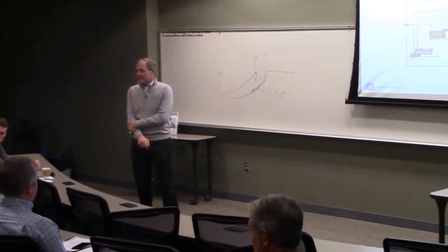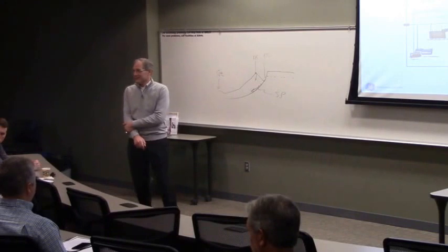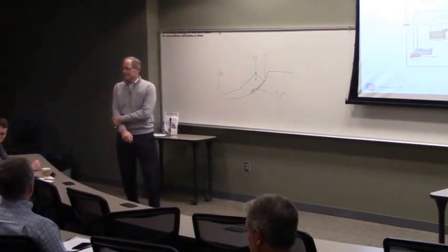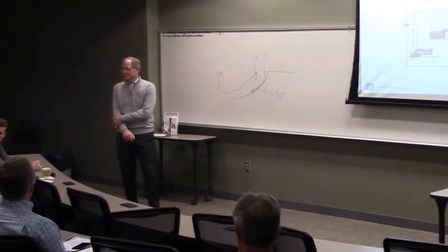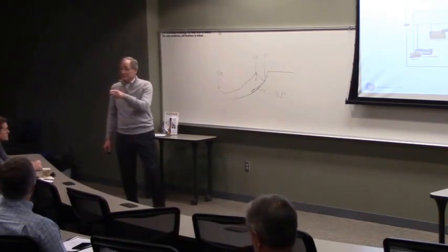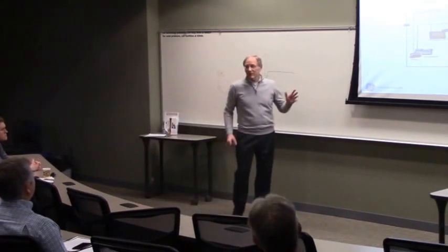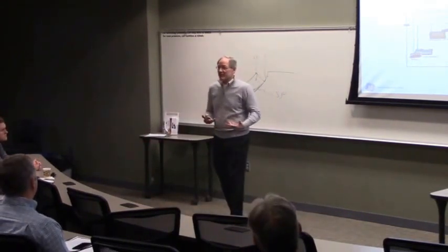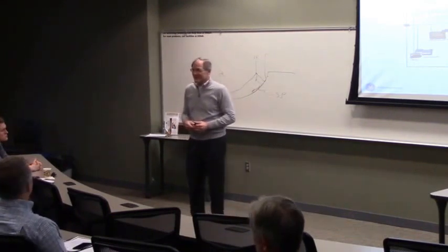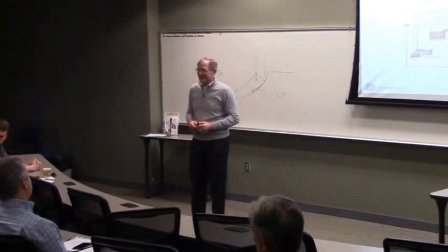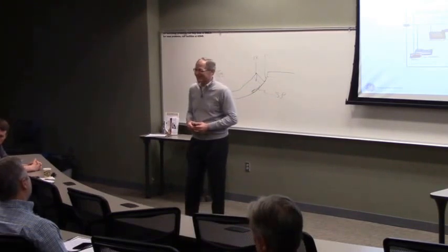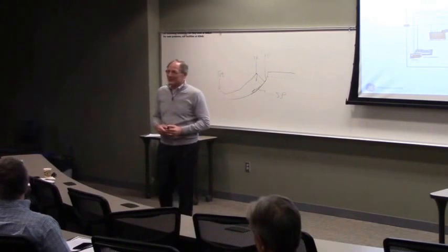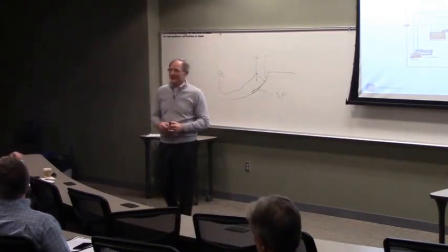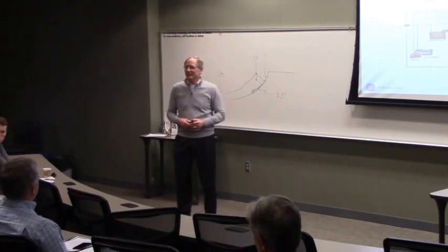The initial standard said the DER shall not attempt to regulate the grid at its connection. Now it says that with the agreement of the EPS operator, you can provide VAR support and/or regulatory services at your point of connection. So before that amendment was passed, we weren't allowed to use the inverter as a VAR resource? No, the standard never said you weren't allowed. It said you shall not actively regulate. And I say that because with synchronous generation, I have always run them at less than unity power factor, which gives you a constant VAR input at the point of connection.